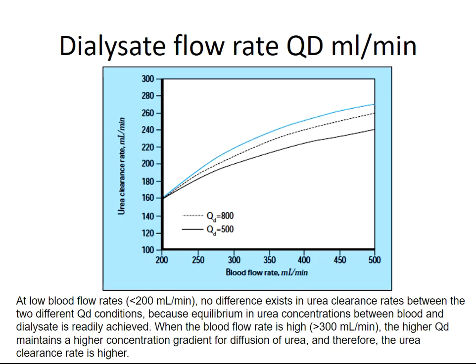Dialysate flow rate does not improve clearance at blood flow rates below 200 mL/min. No difference exists between dialysate flow rate and blood flow rate in urea clearance at low flows, because equilibrium in urea concentration between blood and dialysate is readily achieved. When blood flow rate is high — above 300 mL/min — a higher Qd maintains a higher concentration gradient for diffusion of urea, and therefore the urea clearance rate is higher.